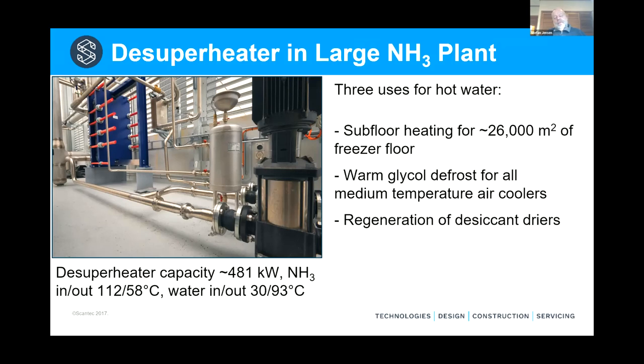Secondly, we use the warm water that comes out from the desuperheater. It's generally about 80 degrees. 90 degrees or 93 degrees, as you see there on the picture, is when we're running 35 degrees condensing temperature. We try not to do that, of course, because it uses too much energy. So we let the condensing temperature float. And then the available temperature from the desuperheater floats down with it. So in all the glycol air coolers for the medium temperature services, we have a little heat exchanger so that we can run warm glycol defrost for all the medium temperature air coolers.